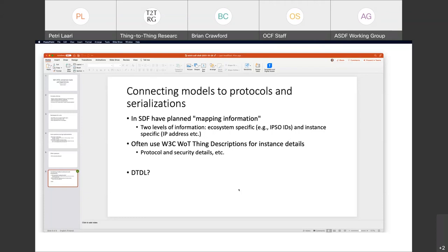We actually have two different ways of looking at these. The device-facing binding: a device will be implemented using some protocol like MQTT, BACnet, or Modbus, communicating outward, and we want to map that into model elements. On the service side, typically services are REST-based using HTTP. We've actually got a mapping described with Swagger — we have a published Swagger that defines the service-facing side. Thing Description has all the same elements of Swagger but puts a semantic description up front with data schemas and protocol bindings.